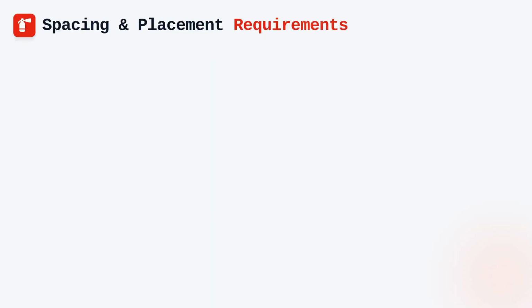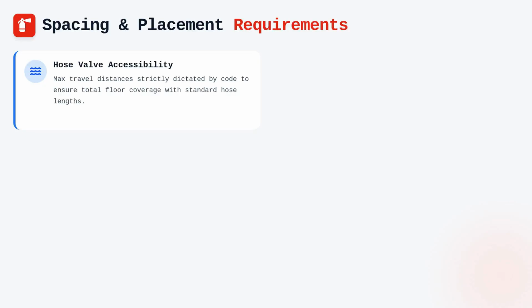Spacing and placement are equally important to the hydraulics because a system is only useful if it is accessible to the personnel who need it. Code requirements typically dictate maximum travel distances to hose valves, ensuring that a firefighter can reach any part of a floor level with a standard length of fire hose.